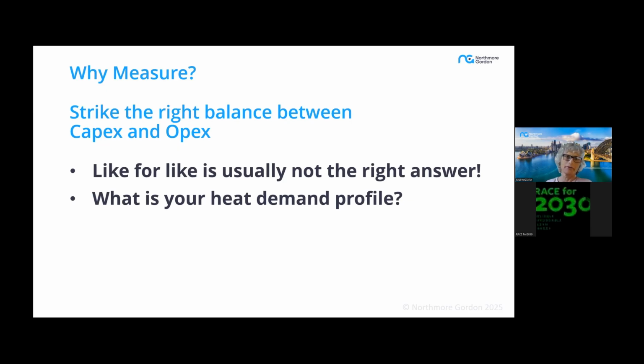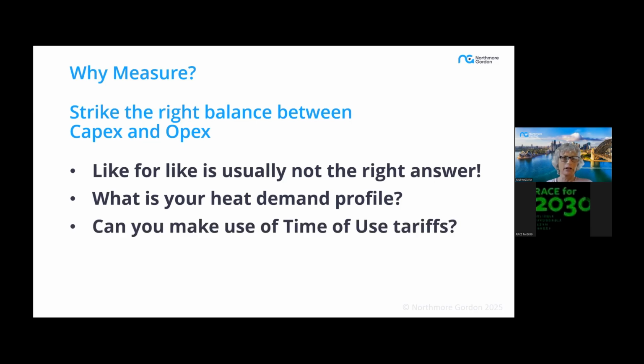So the important question is, what is your heat demand profile? That can only be understood well by metering either your gas consumption at a granular level, or metering your flow and temperature in your water system. And that's important to be able to understand exactly what your needs are in terms of heat. And also it helps you understand whether in the use of a heat pump, you can make use of time of use electricity tariffs. So by understanding it well, you can actually improve the business case.